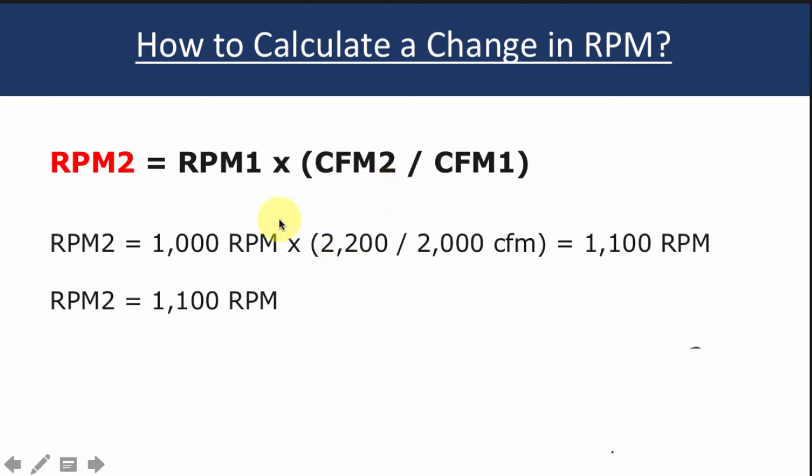So the good way to remember this is 2 is new, 1 is old. 2 is always the new number you're looking for. 1 is the old number or the existing number. It's a little mnemonic to help you remember what is new, the new number and what is the old number. So in this case, we had 1000 RPM existing, RPM1. CFM2 is the new CFM we're looking for. CFM1 is the old existing CFM. You just do that calculation and to get the CFM we want, we need to speed the fan up to 1100 RPM.